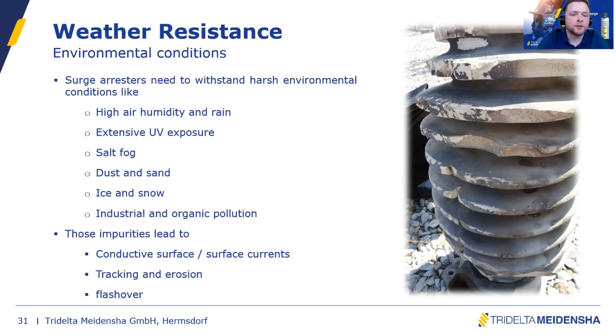We have ice and snow, and we have to consider industrial or even organic pollution, which takes place on the surge arrestor surface. Those impurities on the surface can lead to conductivity, and then surface currents flow across the surge arrestor. And we will have more or less a kind of tracking and erosion process on the surface that is damaging our surface and decreasing our potential insulation withstand of the housing itself.